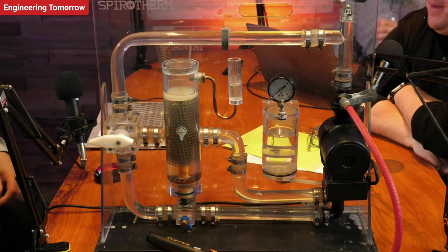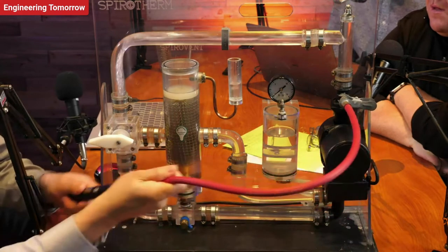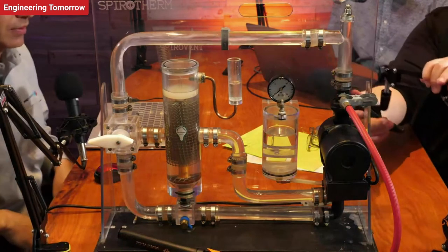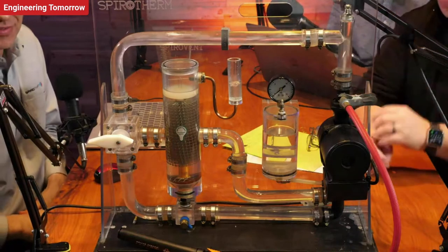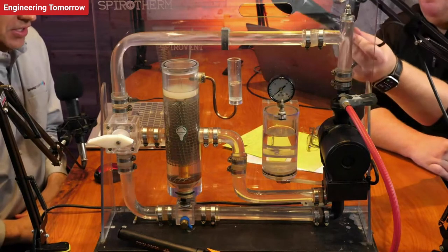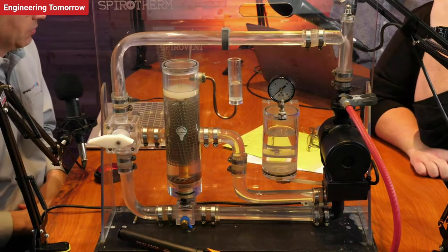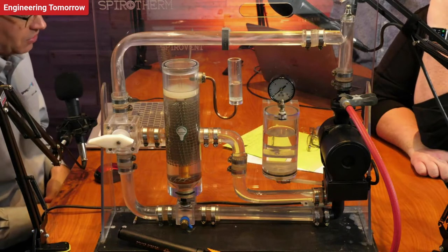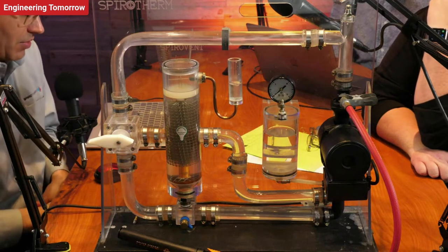So I'm going to inject some air — just a couple of shots. Now we're seeing tons of bubbles, it's loud, tons of air moving through. This is, unfortunately, how most systems run that don't have a coalescing separator. It is working — it's still circulating fluid, still transferring heat, but you hear the hum of the motor and the cavitation.